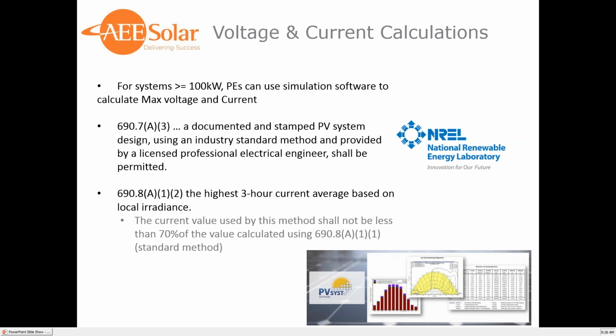690.8A12, the highest 3-hour current average based on local irradiance. So a PE can use simulation software to simulate the system and look at the PV source circuits and model what amperage the conductors will see per local irradiance. So this current value shall not be less than 70% of the value calculated using 690.8A11, which is our standard method, which is just the module ISC times 1.56. So this value cannot be less than 70% of that.